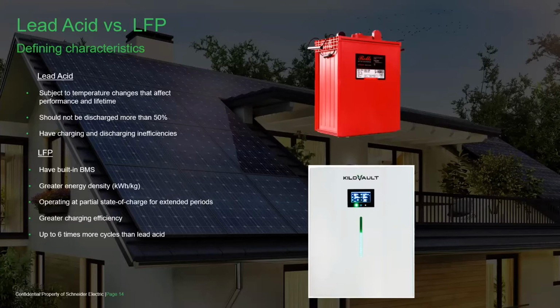Regarding lithium iron phosphate, they do have a built-in BMS. When we talk about safety, a lot of people have been reluctant to go with lithium because it's a volatile chemistry, they can catch fire. But I've never seen that happen with any of our systems. I've heard reports of it happening here and there, but very, very rarely. That's what the BMS is for: it's designed to monitor cell temperature and disconnect the battery from the load or charging source if the cell temperature gets too hot, or if voltage gets too high or low, or if current is too high. Those are the criteria that would trip a BMS.